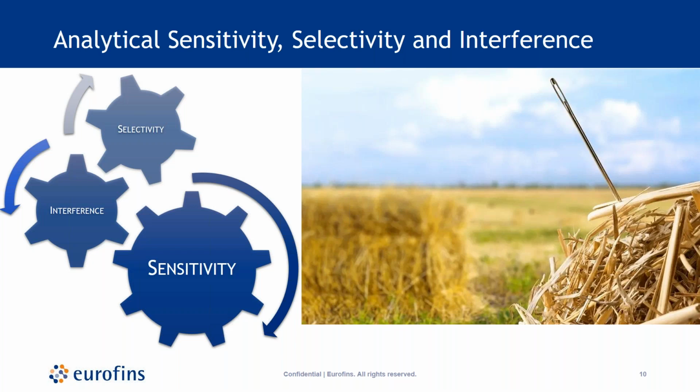Selectivity is the extent to which the method can be used to determine particular analytes in mixtures or matrices without interferences from other components having similar physical properties, which is very similar to interferences, which are spectral, physical, or chemical interferences that can be evaluated by analyzing samples containing various suspected interferences. So you would want to make sure that you're checking every different variation of a particular formulation if you do have multiple formulations for a single product. Carryover should also be considered when evaluating blanks and standards and reference material.